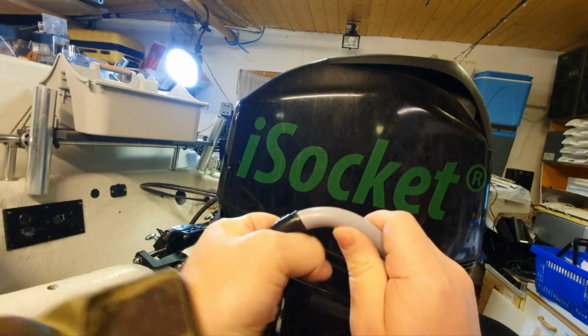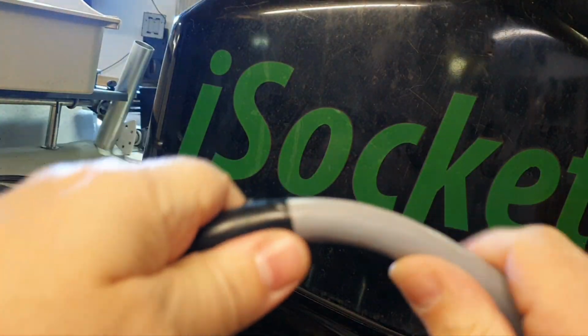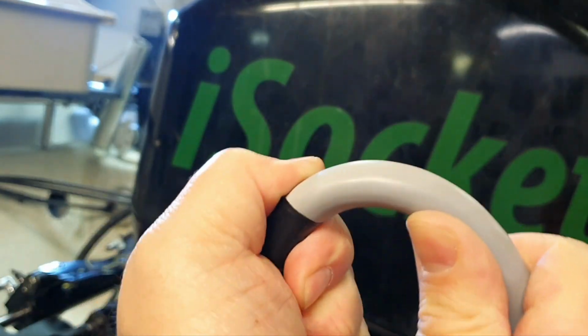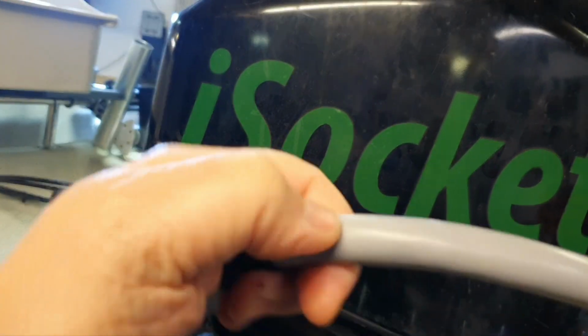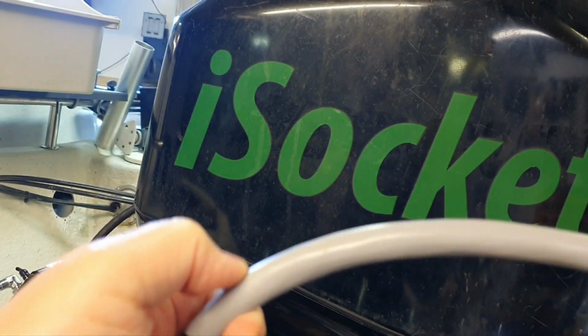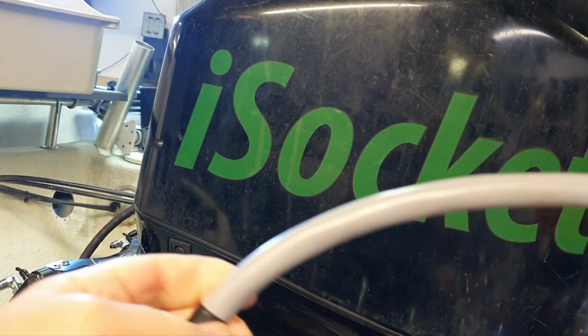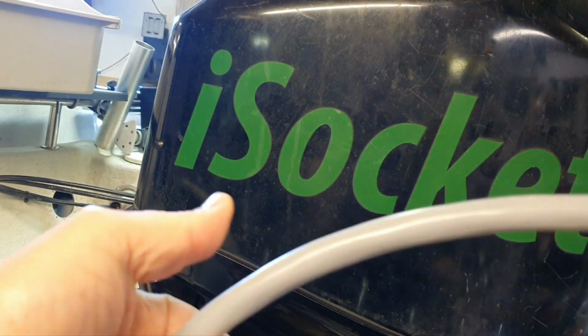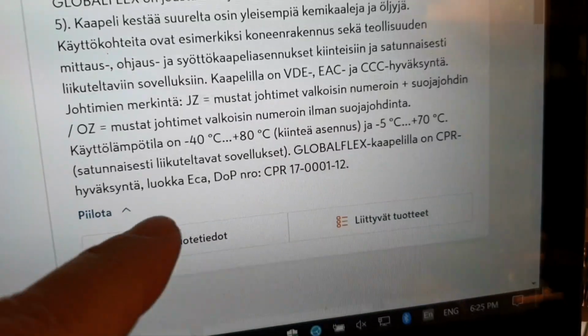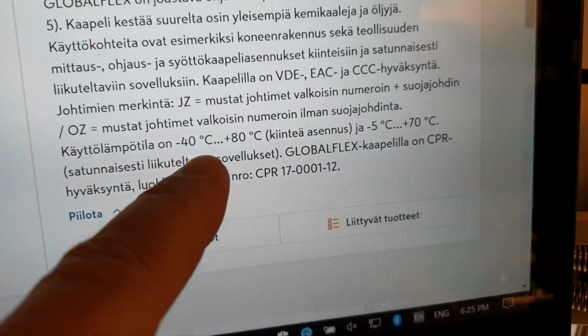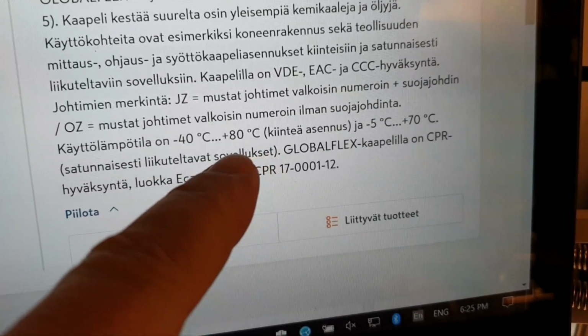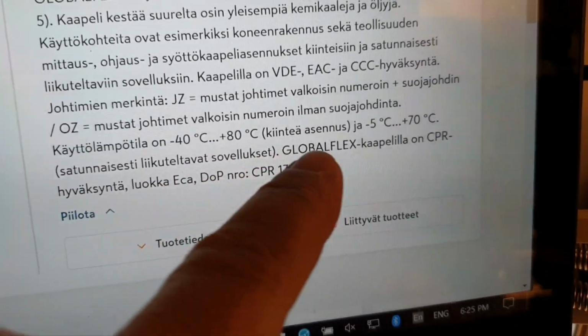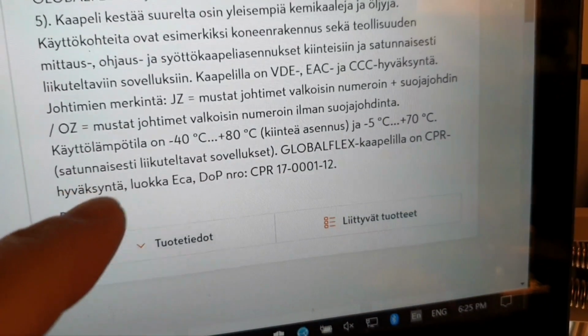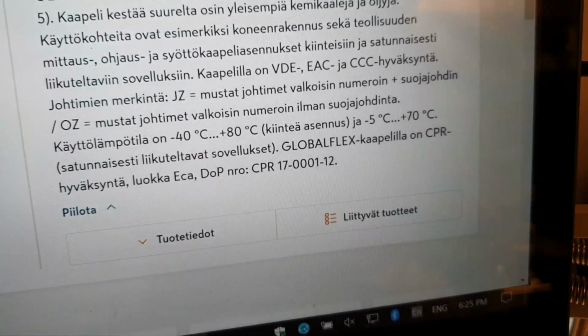Oh, I can't even bend it. Well, but otherwise, at least I cannot break it. And maybe I shouldn't, because usually if you have any movement in your installation, they are not rated for minus 40 then. So it's down to minus 40 degrees Celsius if you use it for fixed installation, otherwise minus 5, which is logical because you can damage the insulation.